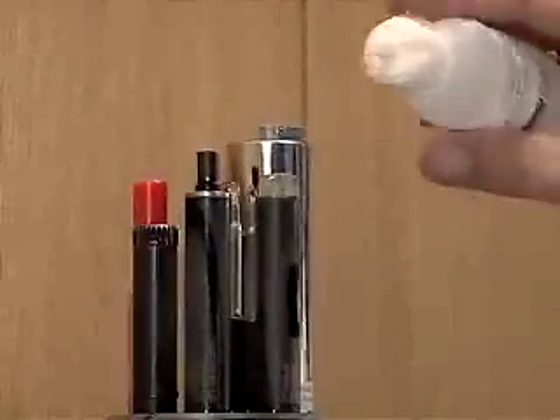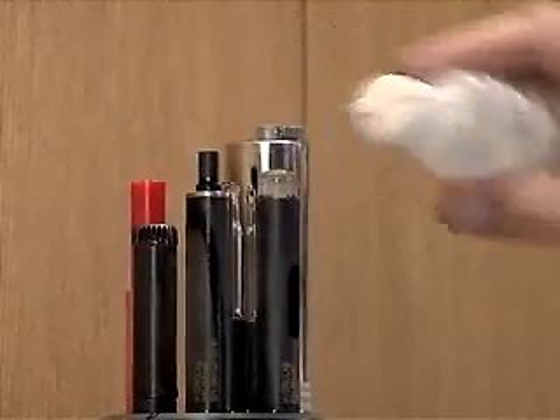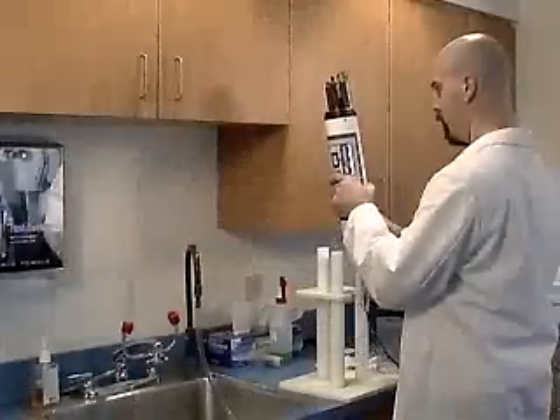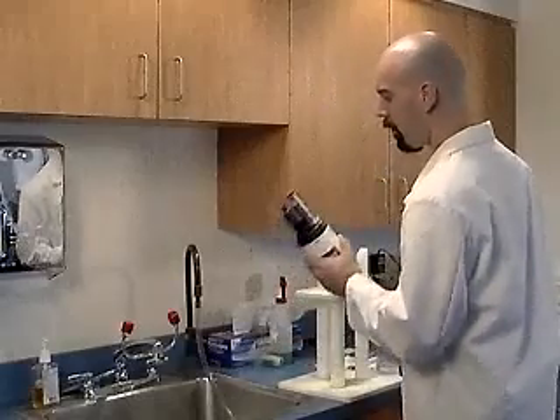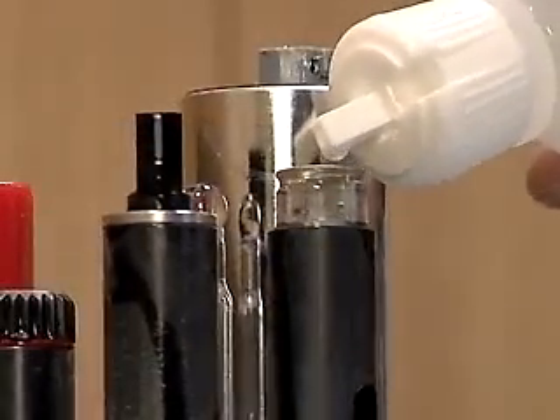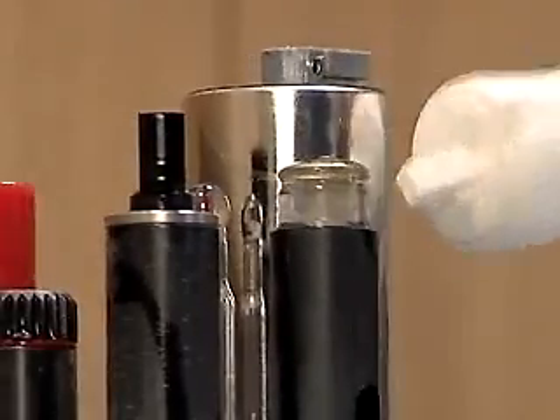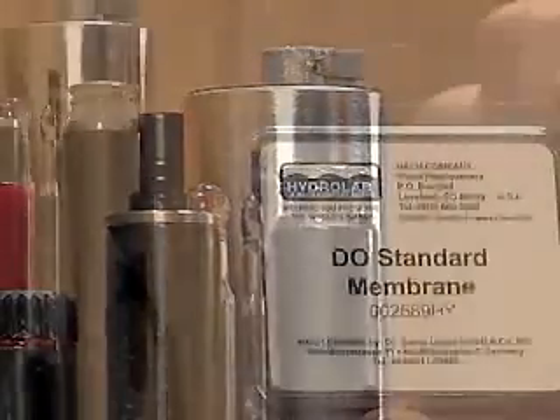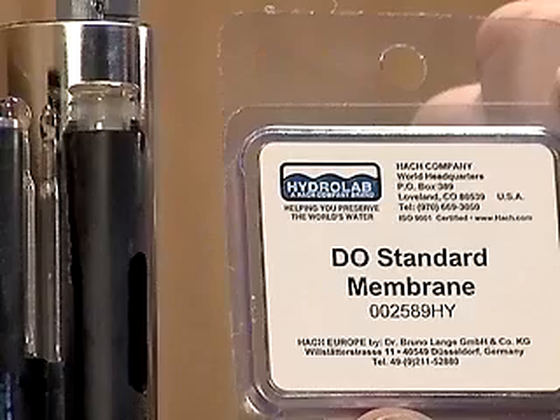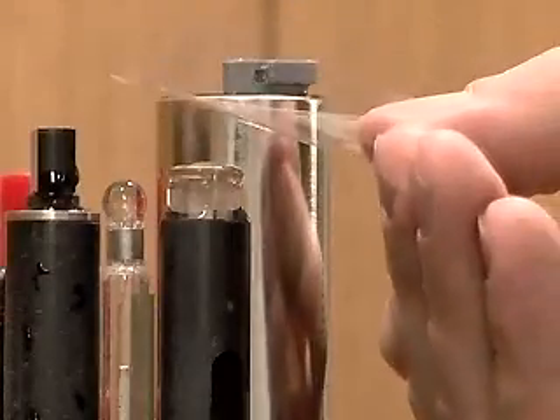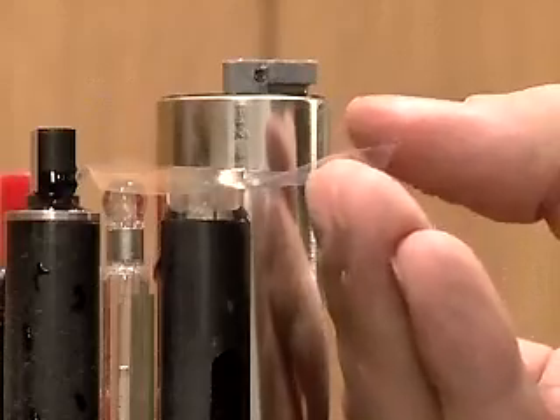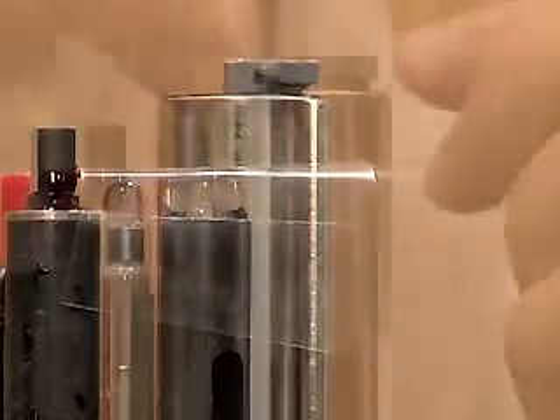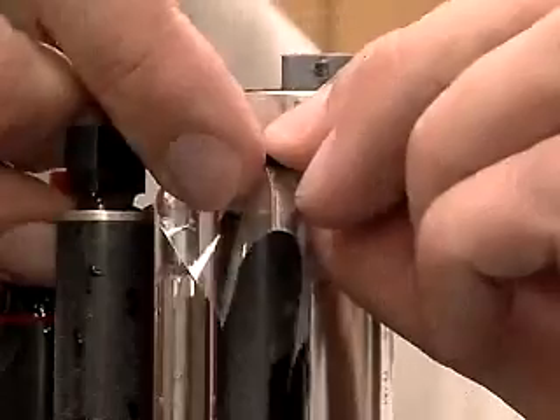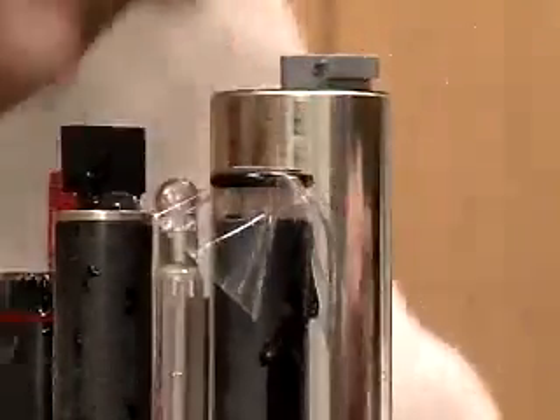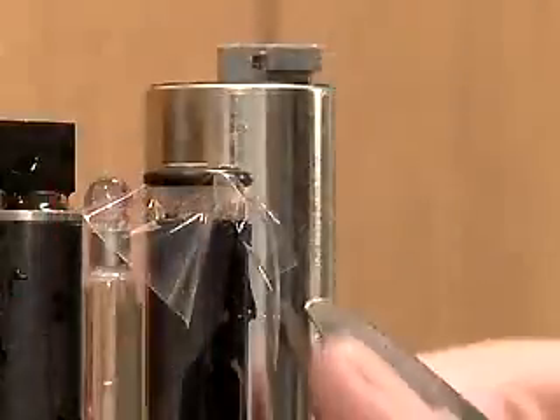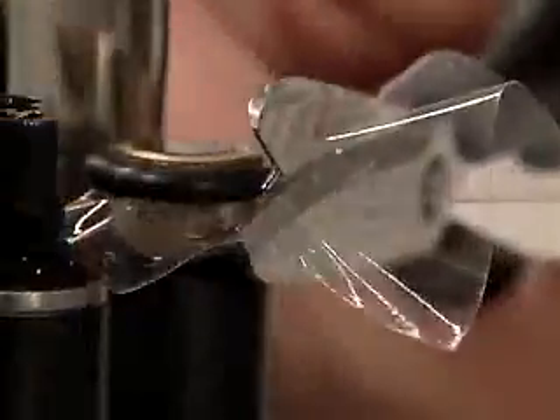When the original yellow shine is restored, rinse the inside of the sensor several times with the DO electrolyte provided in the maintenance kit. Refill the sensor with the electrolyte so that there is a slight dome on the top with no bubbles. Place a new membrane over the top and secure it with the O-ring so that it does not wrinkle and no air is trapped underneath it. If a bubble is trapped under the membrane, discard the membrane and try again with a new one. Trim the excess membrane with scissors.